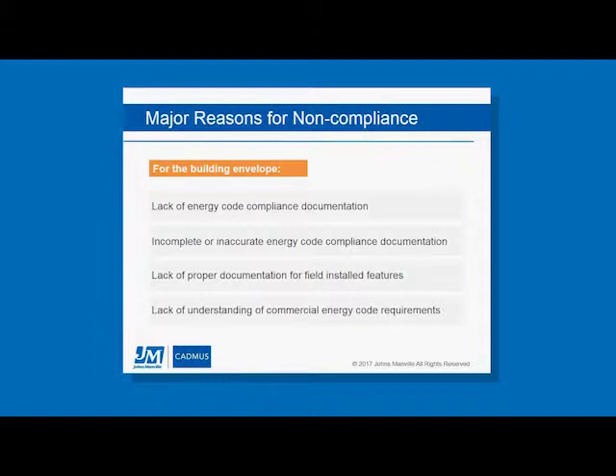You might get a statement on the plans from the designer saying that the building complies with all code requirements of Title 24 or of the IECC, whatever version it's going to be, but there's no documentation that really supports it. And the energy code has a section that says you have to provide documentation in some way, shape, or form that demonstrates that you've complied with the energy code. Sometimes this is, for the envelope, just a cross section through the building that, with leader arrows, points out the different R value requirements, and maybe a glazing schedule that shows U factor and things like that. But oftentimes you don't see that. There's just no documentation whatsoever, and in that case you don't know whether or not the building complies with the code, or if they used a trade-off approach that didn't get submitted with the plan. So that's a big issue.